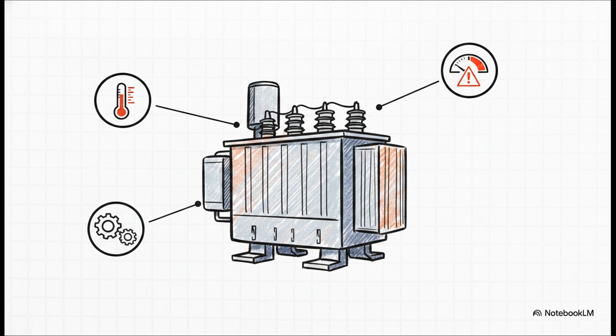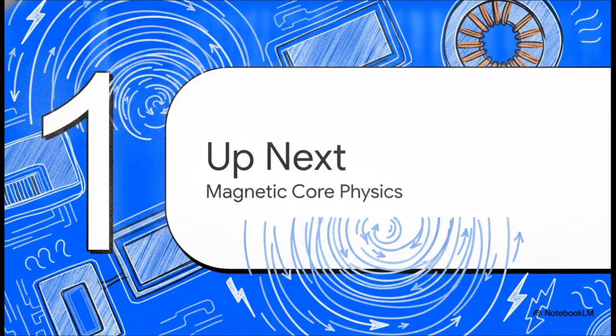You can now confidently read a transformer's mechanical fittings and explain precisely what every single component protects against out in the field. You've got radiators for the cooling, tap changer step rules for the voltage, and pressure gauges paired with those PT100 sensors acting as your early warning dashboard. Next up in the explainer, we are finally going inside the sealed tank to look at the iron core and the copper windings that are doing the actual electrical work.